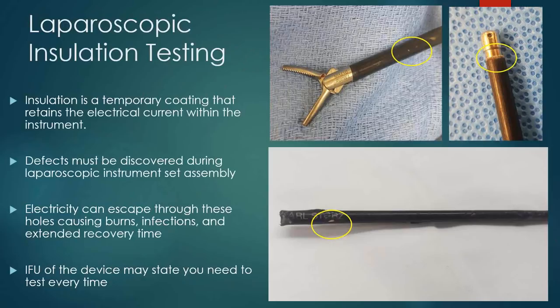Electricity can escape through the holes, causing burns, infections, and extended recovery time. The smaller the leak, the worse the burn, because it concentrates basically in that stray current. The IFU of the device may state you need to test every time. Examples of IFUs for insulated instrumentation devices are going to be on the next few slides.